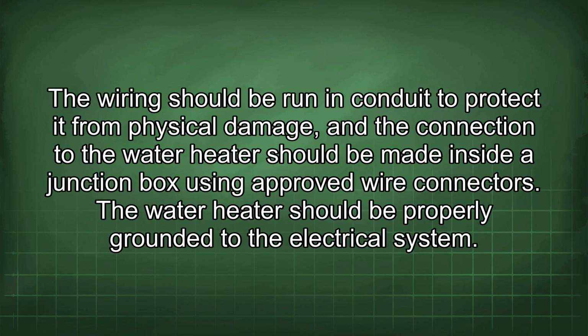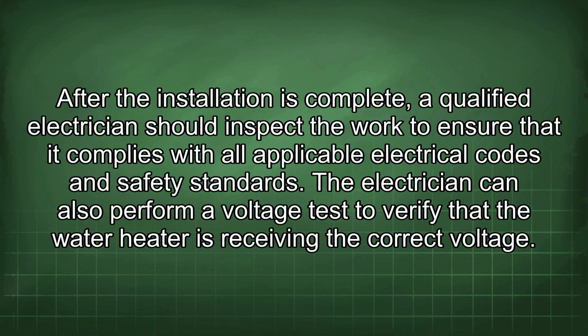The wiring should be run in conduit to protect it from physical damage, and the connection to the water heater should be made inside a junction box using approved wire connectors. The water heater should be properly grounded to the electrical system. After the installation is complete, a qualified electrician should inspect the work to ensure that it complies with all applicable electrical codes and safety standards. The electrician can also perform a voltage test to verify that the water heater is receiving the correct voltage.